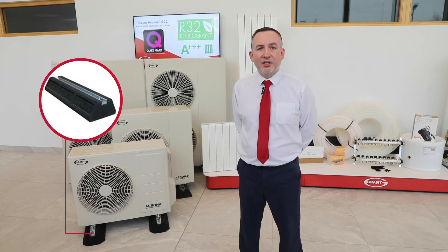The size of the unit required for your new home will be calculated at no cost by our team, along with the additional elements required within the package, as part of our free home heating design service. All Grant Aerona 3 R32 heat pumps are generally supplied with anti-vibration feet and flexible hoses and valves to reduce the chance of vibration being transmitted into the house. The unit itself will be fitted 300mm from the wall and should have no obstructions like fences or enclosures that could restrict the airflow — this is a basic requirement for the unit to operate as standard.